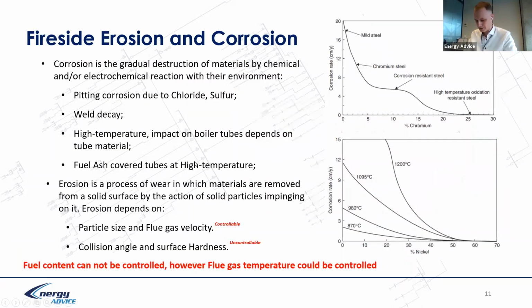Next, corrosion effects. One of the most important and critical issues for boilers is the corrosion and erosion process. Corrosion and erosion are slightly different. Sometimes people just say that corrosion, erosion is a problem, and we have a problem. But in fact, we should separate these questions, because they are different. Corrosion is the gradual destruction of materials by chemical or electrochemical reaction, but erosion is a process in which material is removed from a solid surface by the mechanical action of solid particles impinging on it. So corrosion is an electrochemical or chemical process, and erosion is a mechanical process.